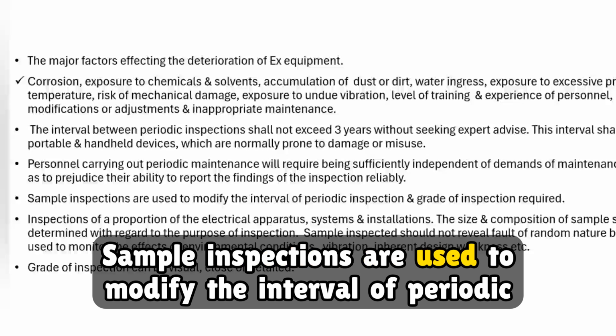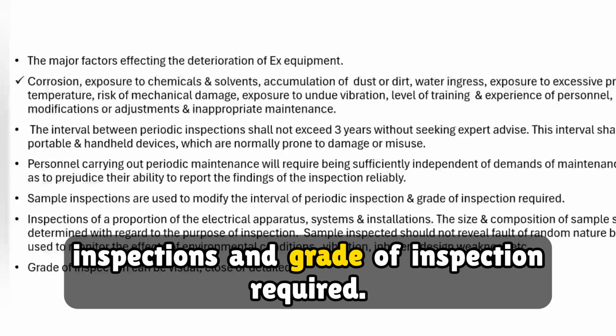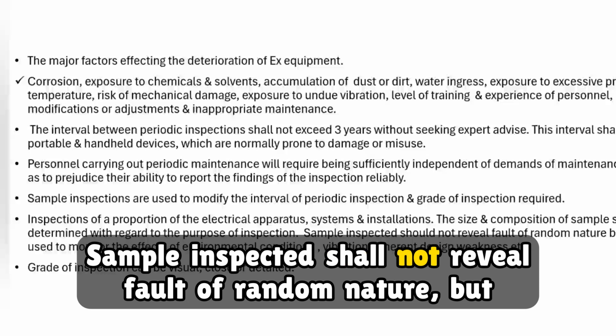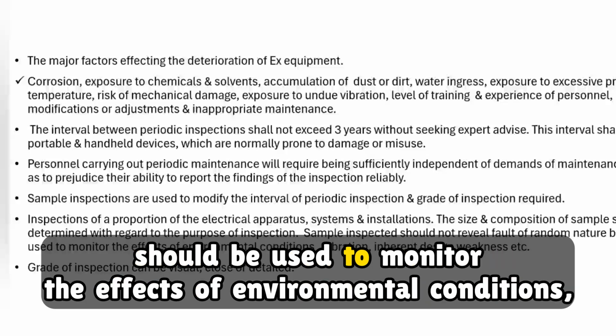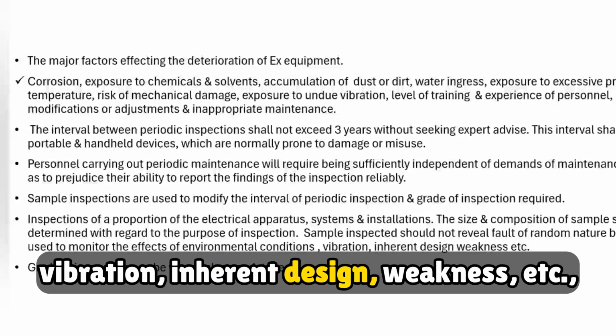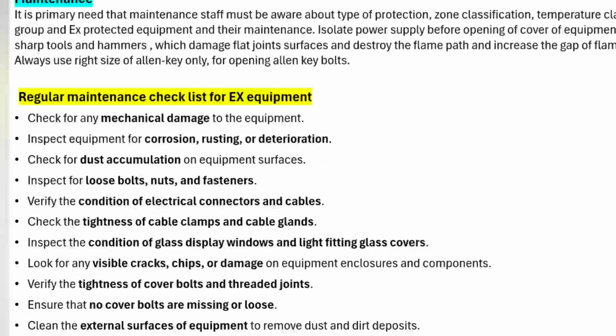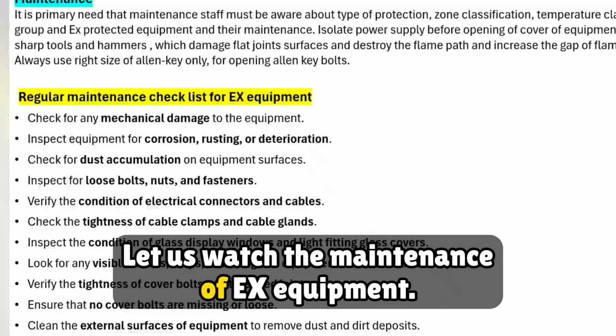Sample inspections are used to modify the interval of periodic inspections and grade of inspection required. Sample inspected shall not reveal fault of random nature but should be used to monitor the effects of environmental conditions, vibration, inherent design weakness, etc. Let us watch the maintenance of EX equipment.